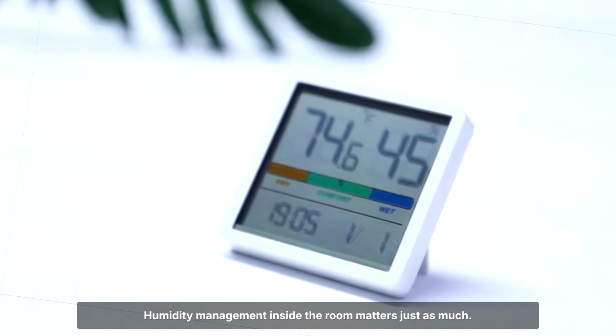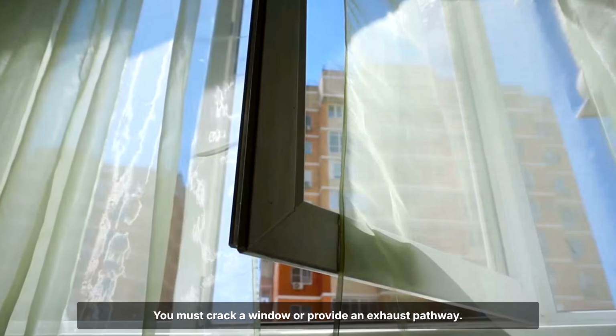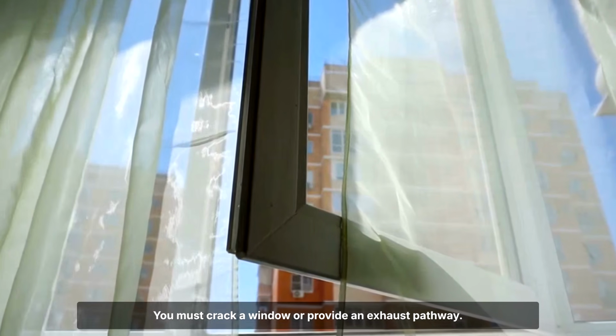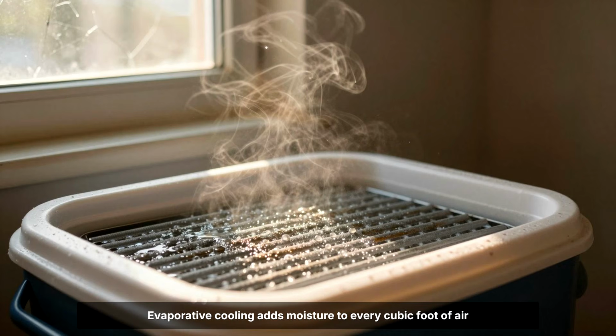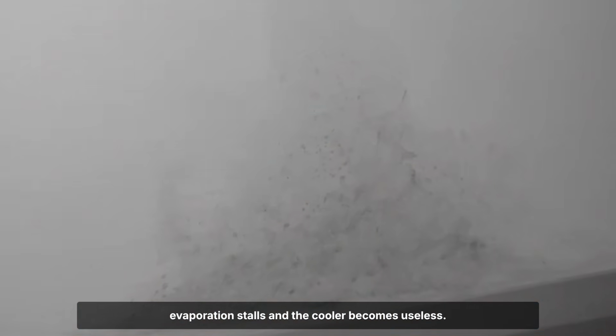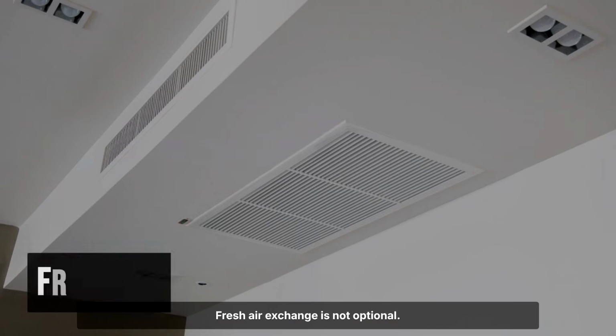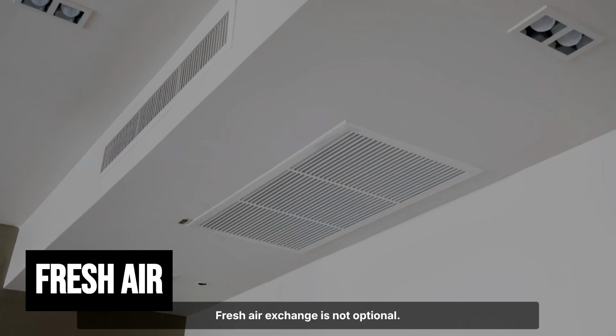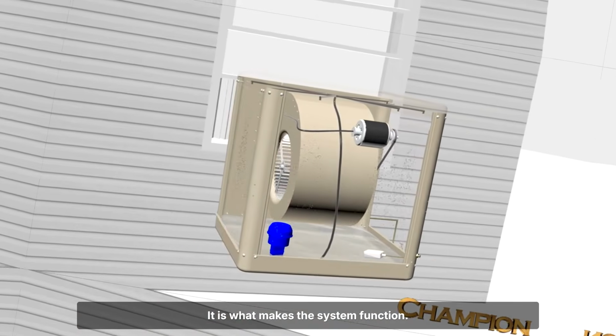Humidity management inside the room matters just as much. You must crack a window or provide an exhaust pathway. Evaporative cooling adds moisture to every cubic foot of air it touches. If that moisture has nowhere to go, humidity builds until evaporation stalls and the cooler becomes useless. Fresh air exchange is not optional. It is what makes the system function.